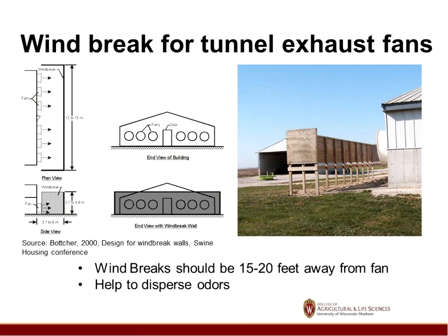A better solution for this is probably to put in a windbreak. So this can become kind of a fence. So here's an example of a fence. 15 to 20 feet away. I might even go 30 feet away. The higher this is, the better. I mean, this is going to be pretty good because any wind coming through here, it's not going to be direct on the fan, but it still could affect it. So having this a little lower would be better.